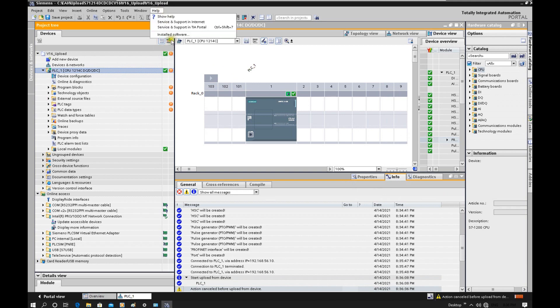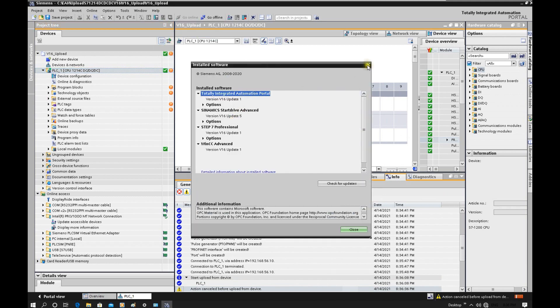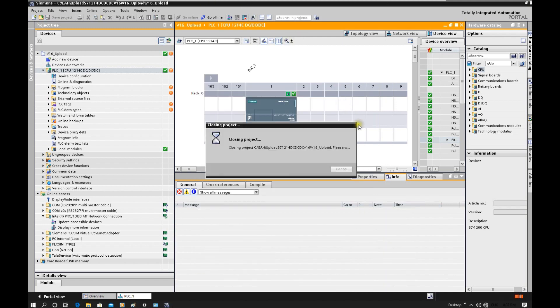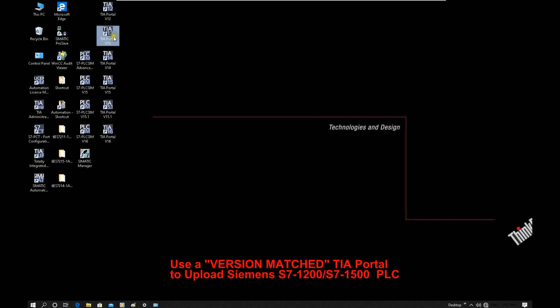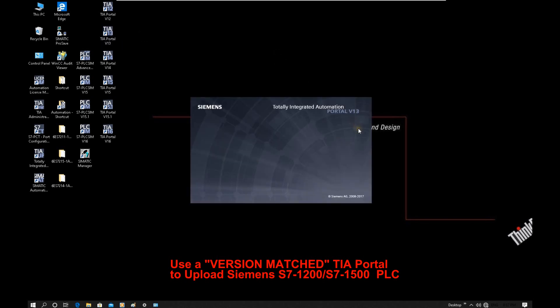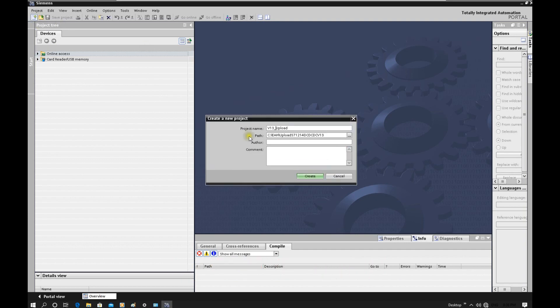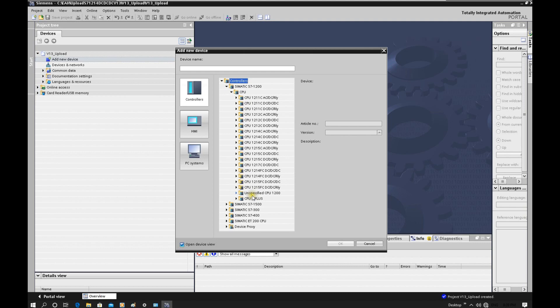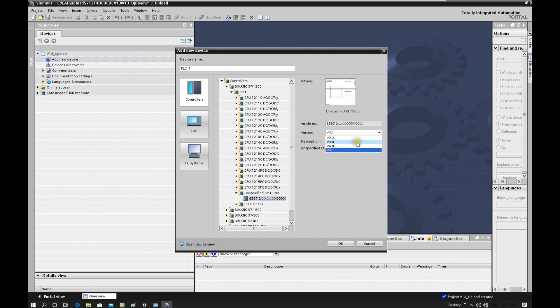So I have to shift to TIA Portal version 13. I will close this TIA Portal and fortunately I have TIA Portal version 13 installed. I will use TIA Portal version 13 — that is the matched version. I create a new project and name it 'version13_upload.' Add a new device. From the previous step we know the CPU firmware is version 4.1, so I will select version 4.1.